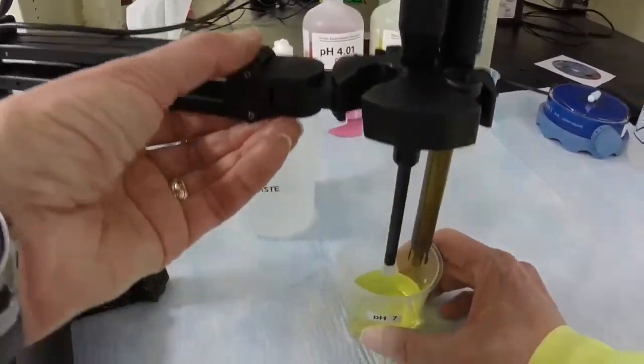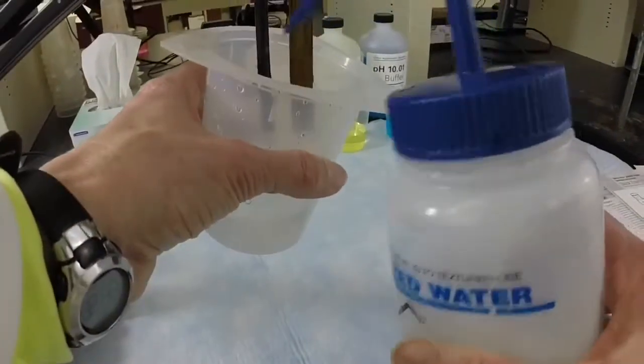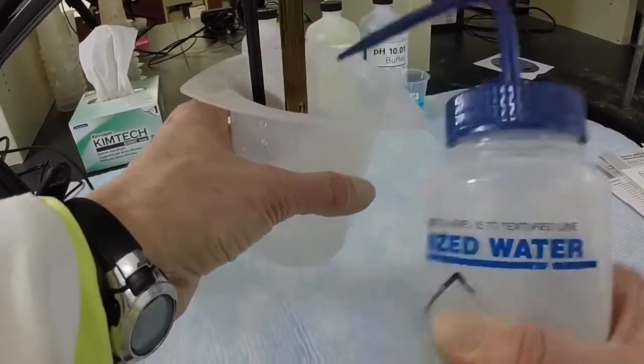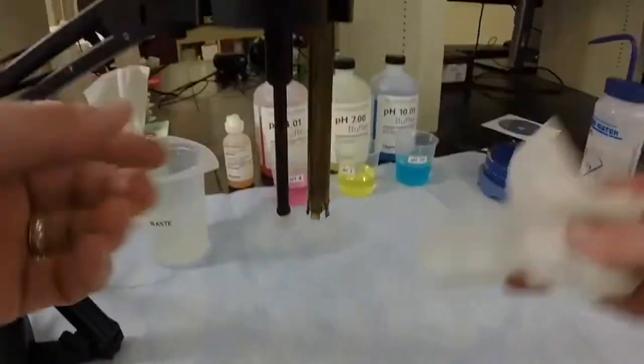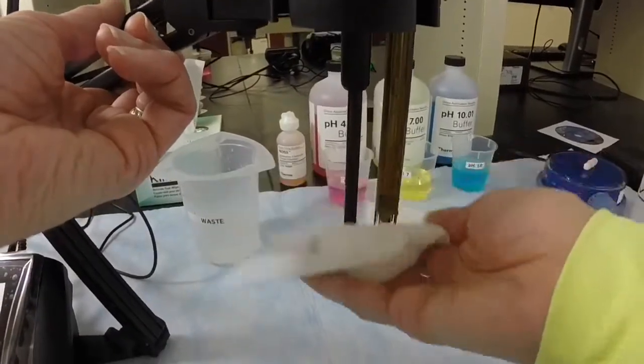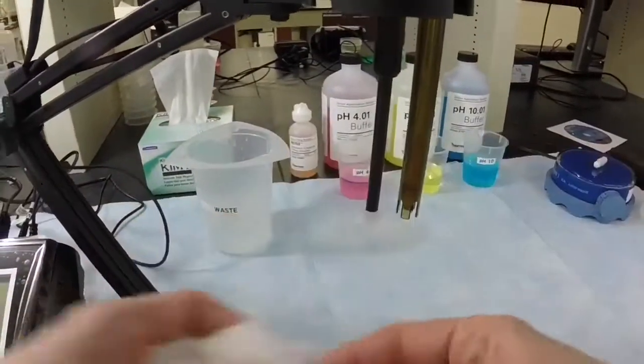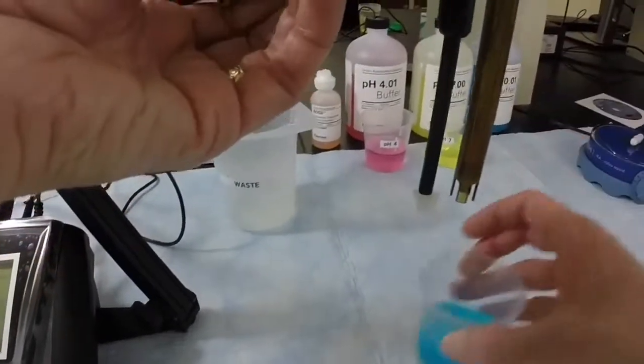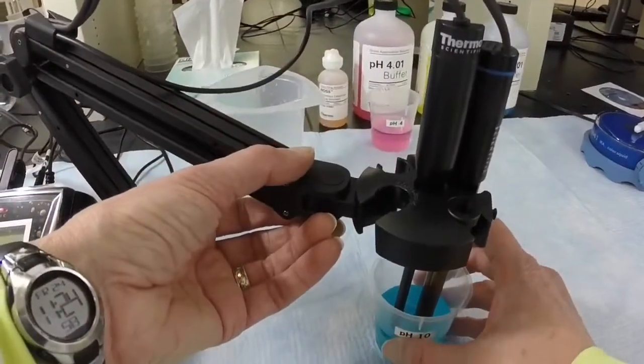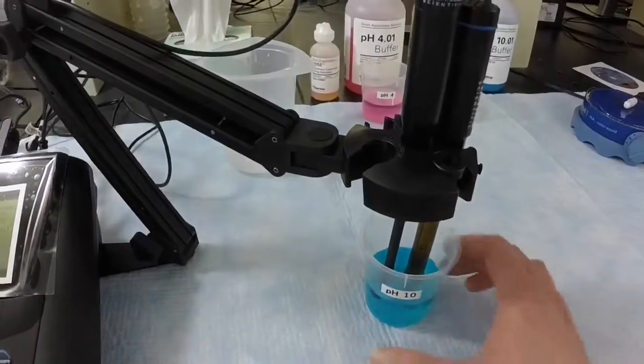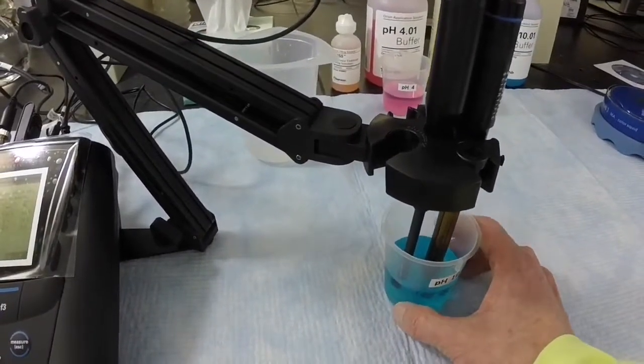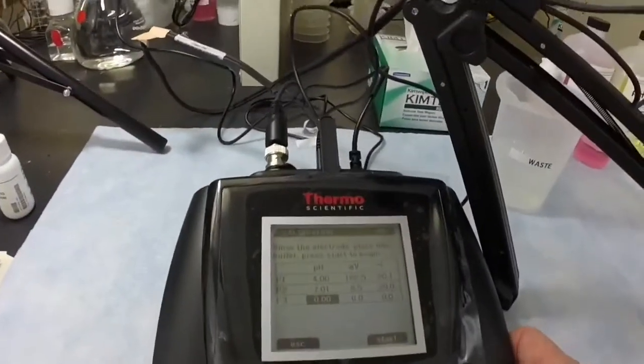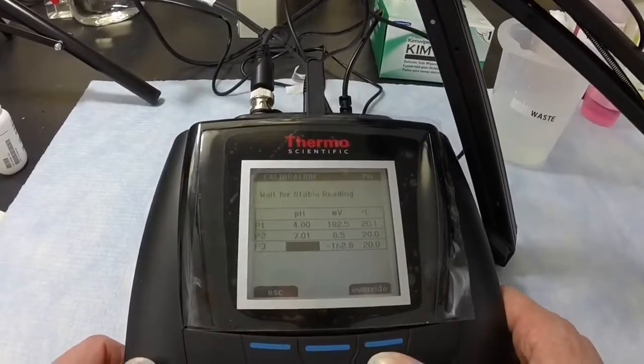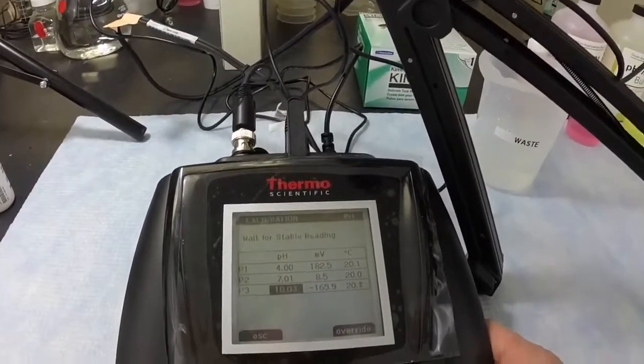Remove the electrode and stirrer from the buffer. Again, rinse well. We want to remove all traces of the buffer. Blot briefly and gently. Insert the electrode and stirrer into the third buffer. In this case, we're using pH 10. Press the Start button. Again, the reading will blink until it is stable.